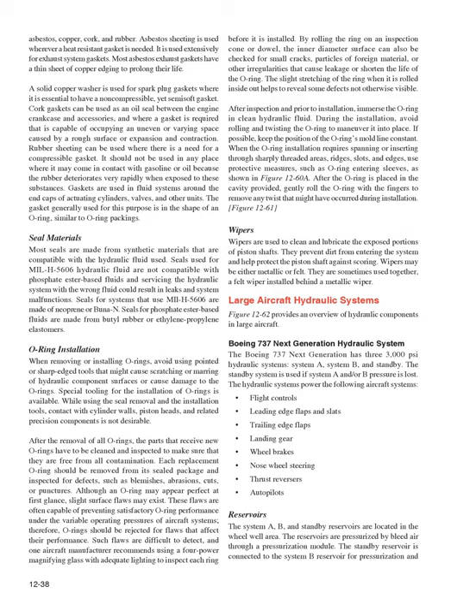O-ring installation. When removing or installing O-rings, avoid using pointed or sharp-edged tools that might cause scratching or marring of hydraulic component surfaces or cause damage to the O-rings. Special tooling for the installation of O-rings is available. While using the seal removal and installation tools, contact with cylinder walls, piston heads, and related precision components is not desirable. After the removal of all O-rings, the parts that receive new O-rings have to be cleaned and inspected to make sure that they are free from all contamination.